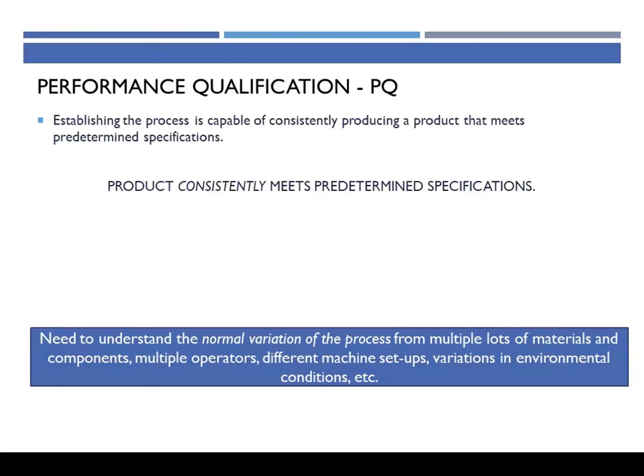Now, in the short run variation is always less than long-term variation, but we need to try and simulate some variation in our process. So over a long period of time, you're going to run that process. It might get run in the cold, dry winters and the hot, humid summers. You might have different shifts, different operators running it. Over a long period of time, you're going to get different lots of material. There'll be different setups. The machine will have had different repairs, different routine maintenance over a long period of time. So you're going to get variation in the outputs of your process. And during your PQ, you want to show a little bit of your process variation.